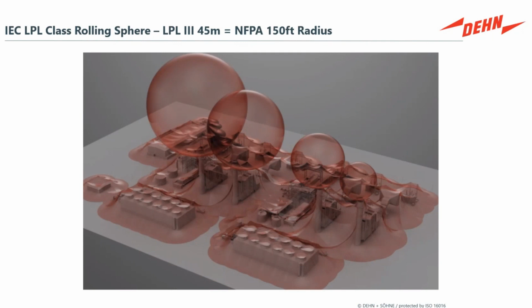So you can picture in your mind's eye a high risk environment, outdoor, charging station, no coverage around. You're out in the middle of a parking lot. You actually have a high risk that if you're charging right at those moments, the lightning might hit the light poles nearby, in which case you have quite a high risk of touch step voltage around the charge station. And the equipment and the human factor are all subject to much higher stress voltage. And that stress makes its way into the electrical wiring, which is the reason you need more or less surge protection. So a smaller radius is higher risk.